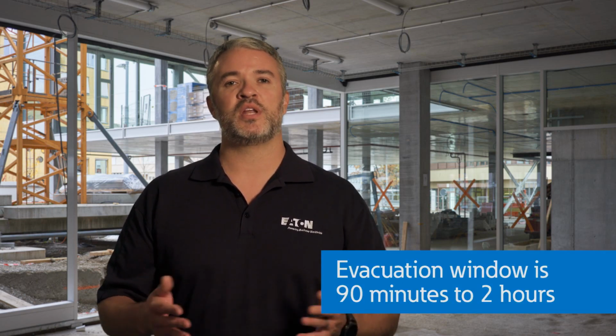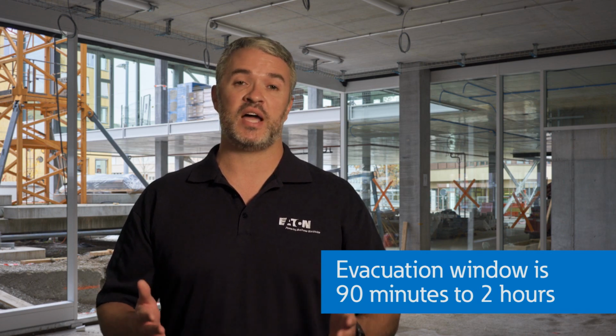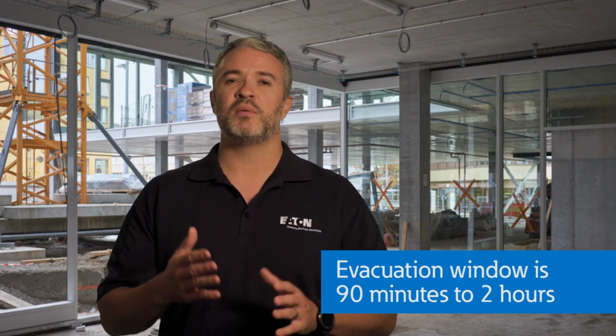Most code requirements for emergency power are intended to ensure that individuals inside can evacuate the building quickly and safely. Typically, this is required within a 90-minute to 2-hour window of time. Often, meeting the minimum building code requirements is not sufficient for maintaining healthcare operations or services when an outage occurs, due to the nature of the occupants.